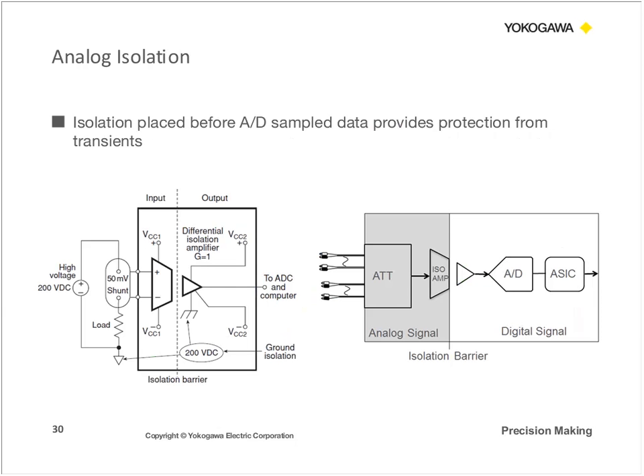So isolation amplifiers, if you recall in the crosstalk example, if you install an isolation amplifier at each channel, you're going to prevent the voltage from bleeding into the next channel. And one other benefit that analog isolation gives you is the ability to protect the A to D converter in your measurement system. It's arguably one of the most expensive parts of the data acquisition device itself.